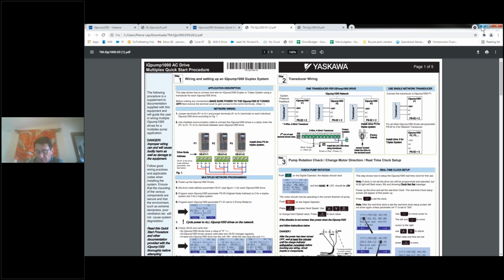One of the other things that I'll say in terms of affecting the design, affecting the performance positively with minimum return on investment, is in the use of inverter duty cable. This is another differentiating factor that will increase the cost of the cable by as much as 50%. So instead of spending $10 a foot, you may be spending $15.